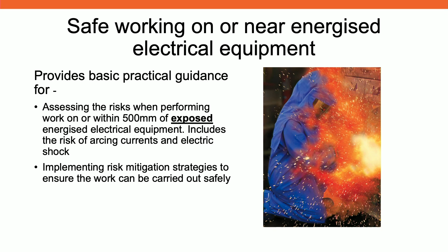So the risks when you're working within 500 millimetres from arc flash or electric shock are pretty much the same as when you're working on it. So the exposed part is probably the critical thing to understand. Anything that is less than IP2X, as in anything that a person can touch with a finger, and the finger is based on the standard test finger. So if there's more than a 12 millimetre gap that you can get something in, then it will be an exposed part. The book will give you a guide on implementing risk mitigation strategies to ensure the work can be carried out safely. So it's all about when you have to do work in that area, then you can actually implement things to do it safely.